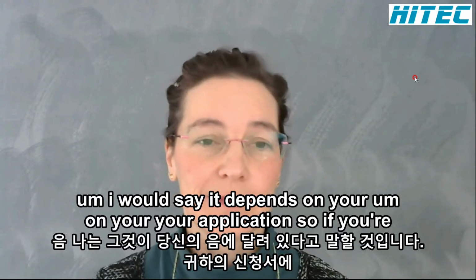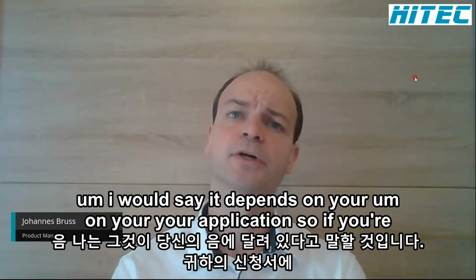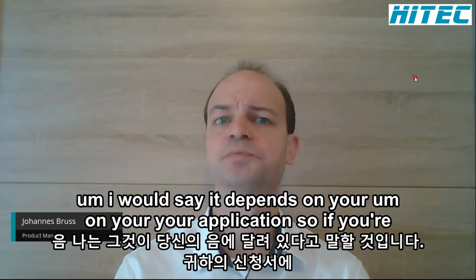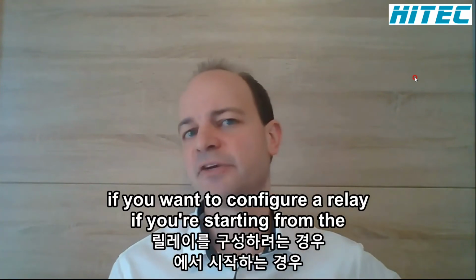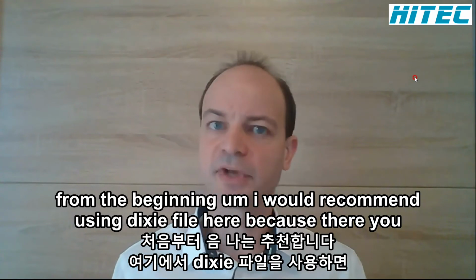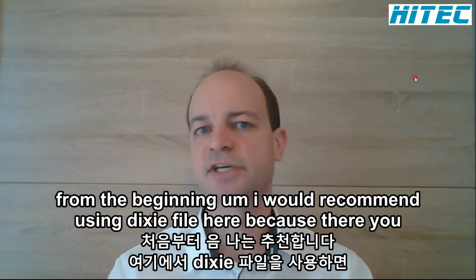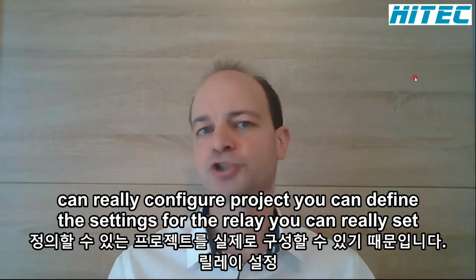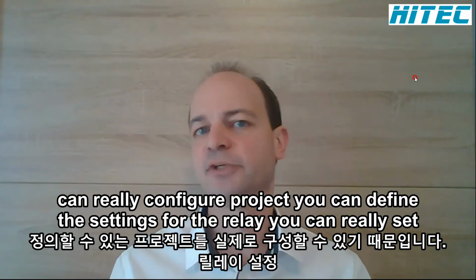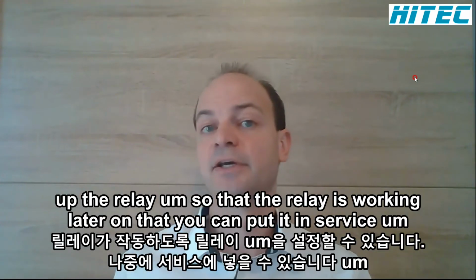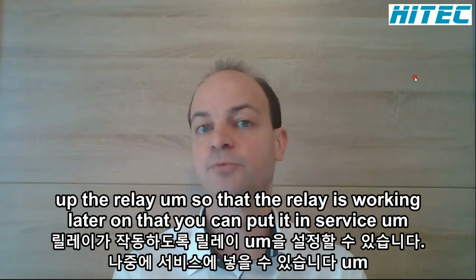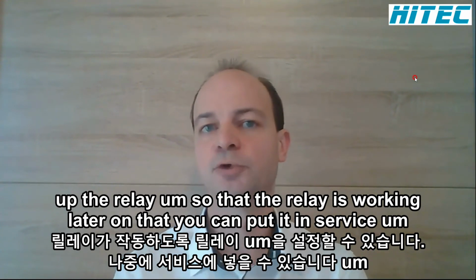I would say it depends on your application. So if you want to configure a relay, if you're starting from the beginning, I would recommend using DIGSI 5, because there you can really configure a project, you can define the settings for the relay, you can really set up the relay so that the relay is working later on, that you can put it in service.